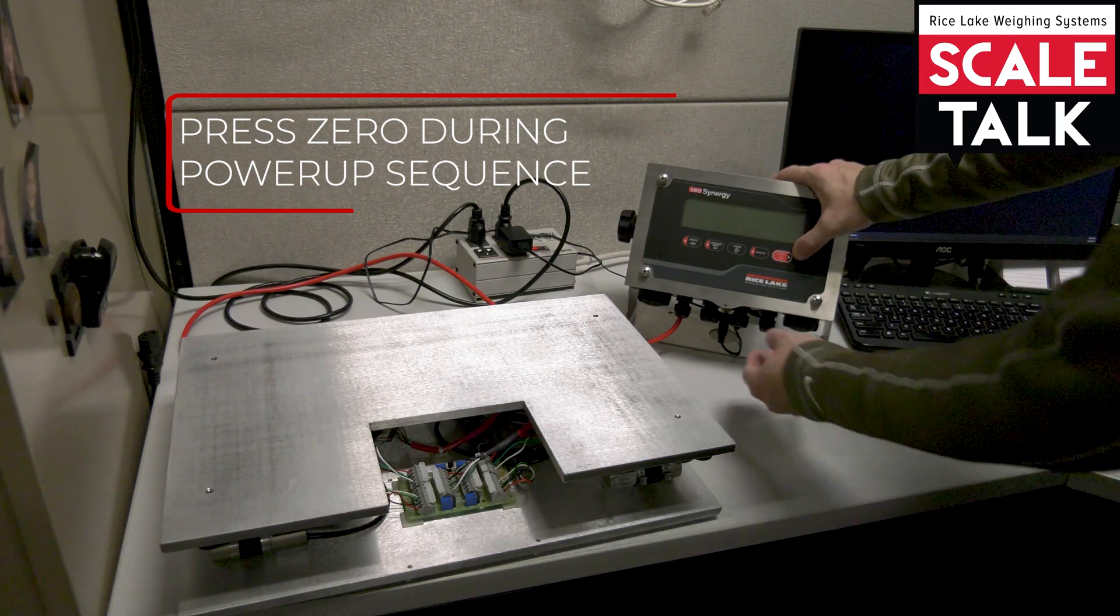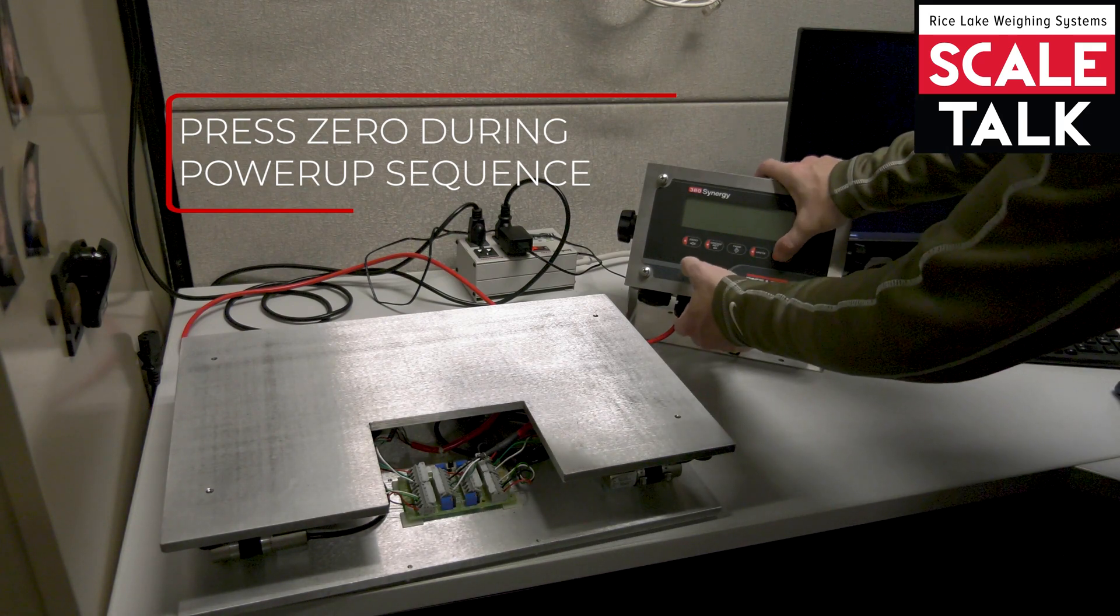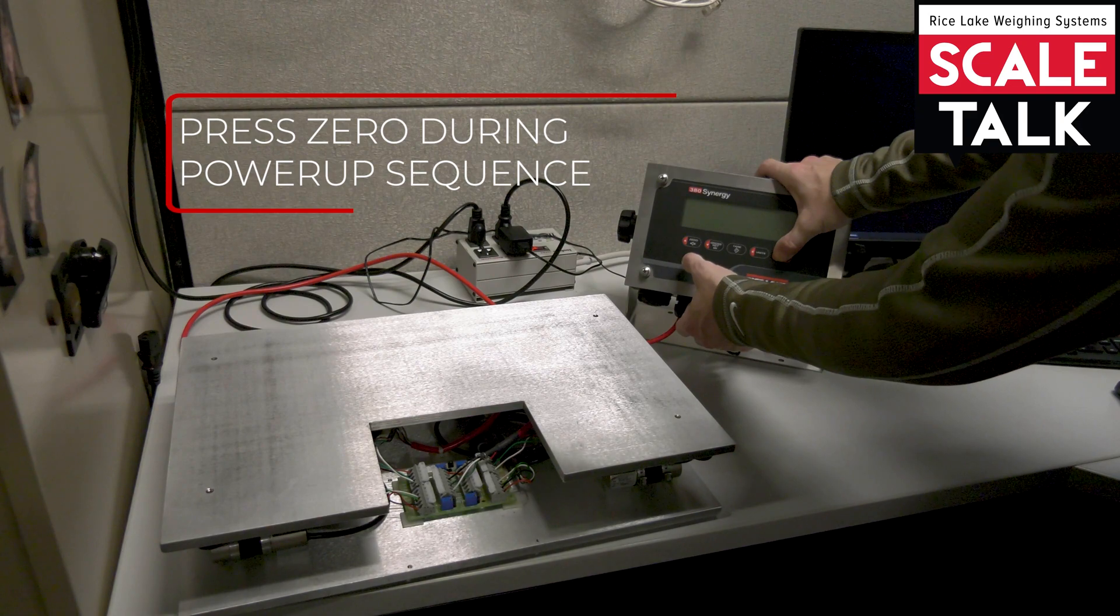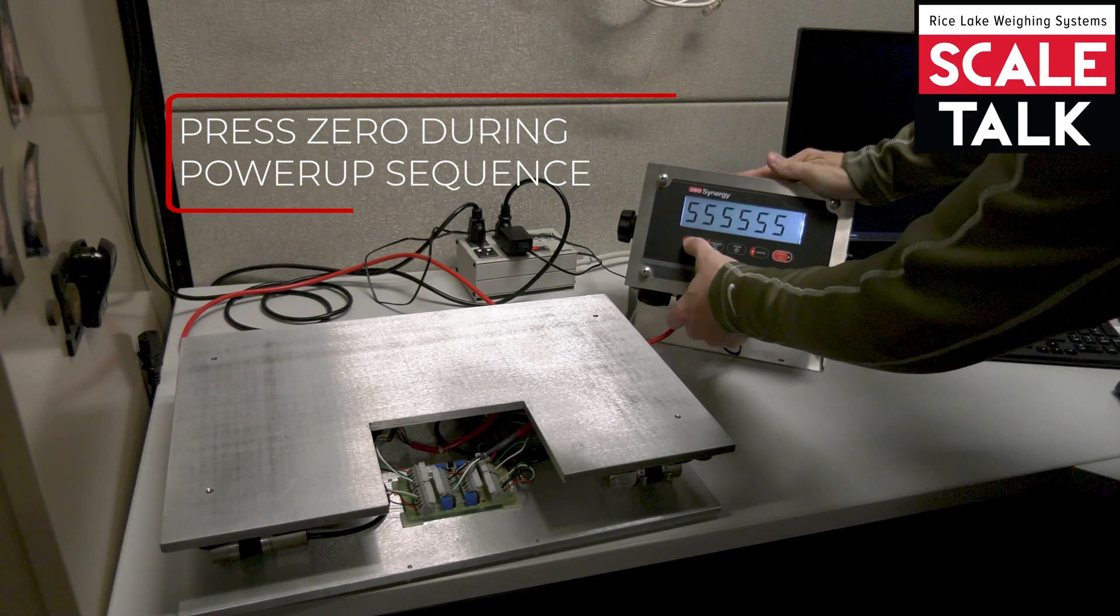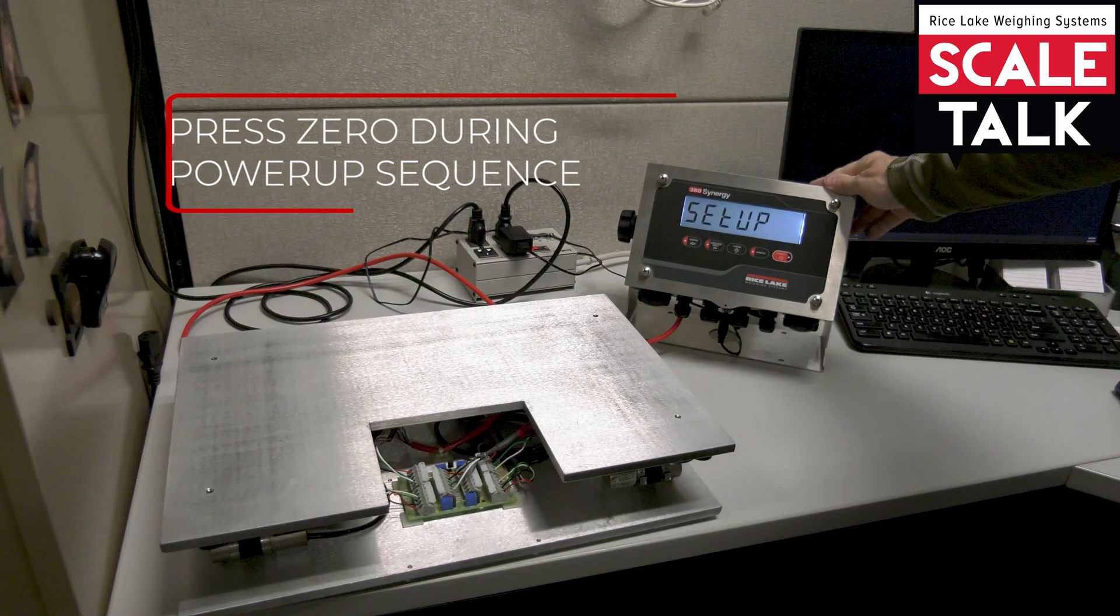So I'm going to press and hold that print button until the scale lights up. During the count up I'm going to press zero and now I'm into the setup menu.